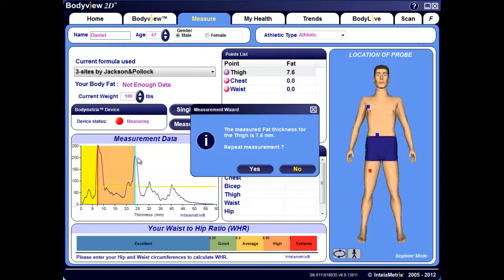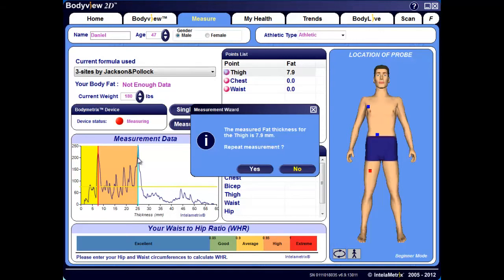Next, we'll demonstrate measuring without using the averaging technique. In this example, we'll press the button for a fraction of a second without moving the Bodymetrix device. The resulting measurement data graph shows an unaveraged signal with many fine, thin peaks representing various tissue structure. Keep in mind that the Bodymetrix transmits a narrow beam of ultrasound that detects tissue structure along that beam, so it's very important to move the device and average a signal because it eliminates the fine structure — which is not of interest when measuring fat layer thickness — and leaves you with clean interfaces such as the fat-muscle interface or muscle-bone interface.